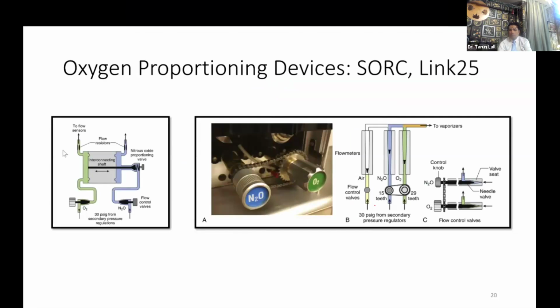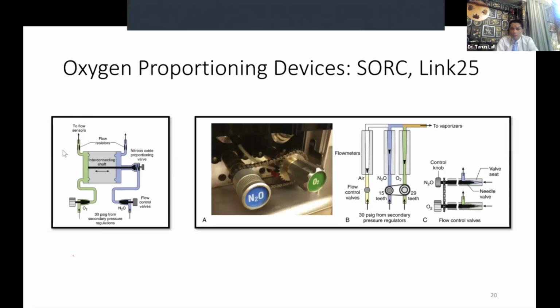Another safety feature in the anesthesia machine these days is the oxygen proportioning device, and we have two common types: the SORC, that is the sensitive oxygen ratio controller, and the Link-25. SORC is usually seen in Dräger machines. Here you can see the blue line is nitrous and the green line is oxygen. Because of the oxygen pressure, this piston is pushed that side, which allows the proportional amount of nitrous oxide to flow. As the oxygen pressure falls, the nitrous pressure also falls. So that is the sensitive oxygen ratio controller used in Dräger devices.